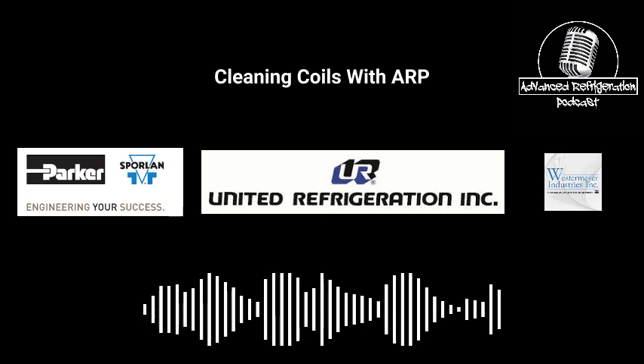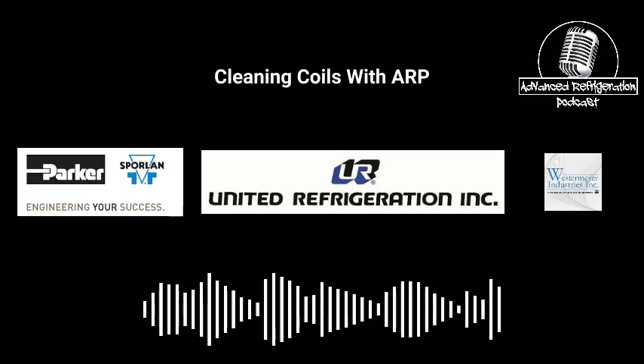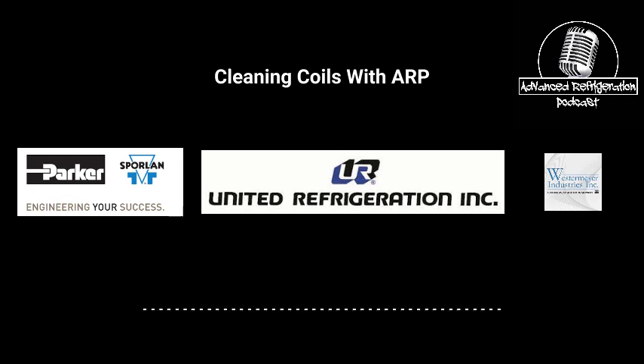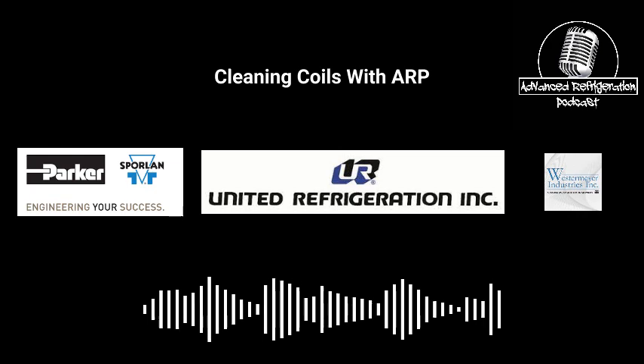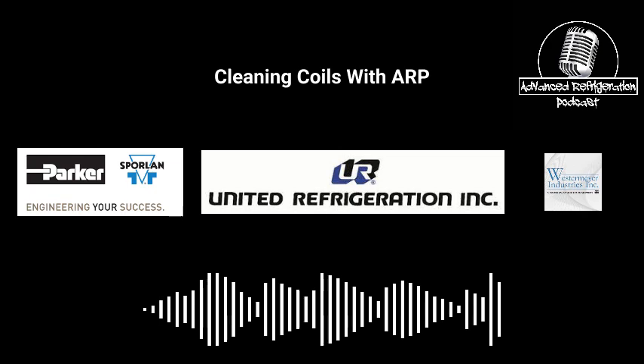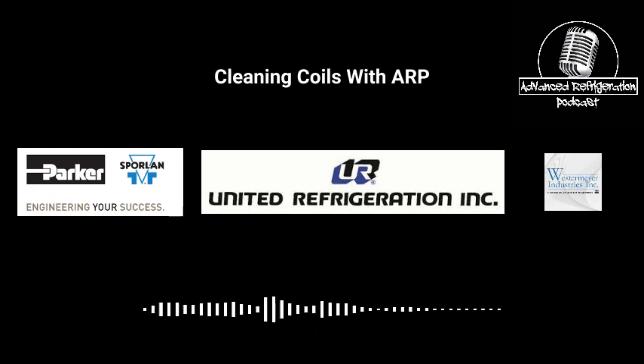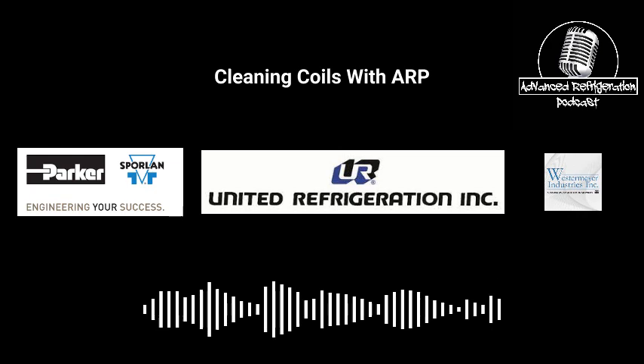And then your sanity is going to be better, because you're not running service calls at 2 o'clock in the morning because racks are tripping on high head, and having to go out there and reset stuff and clean coils and find motors that are out. Nobody wants to do that. Or you're going to have motors overheating and randomly knocking racks out. Especially if you guys are apprentices, get up there and get those coils cleaned. Write it down. Take pictures of what you did. Nobody's harping on you for cleaning coils to keep the service calls away.